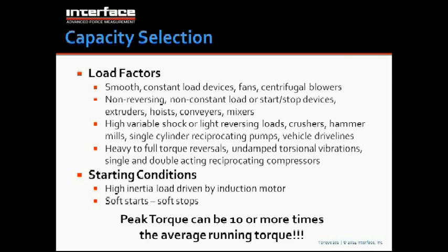Then you also think about starting conditions. If there's a high inertial load and you start a motor, sometimes you can exceed the rating of the motor dramatically. There's a startup torque that's much higher than the running torque of the motor. And the way to prevent that would be to start softly. Also, if you were to hit an emergency stop, and shut everything down very quickly, the rotary inertia can overload the system before it shuts down. Just remember, peak torque can be as much as 10 or more times average running torque, so it's very important to consider it.